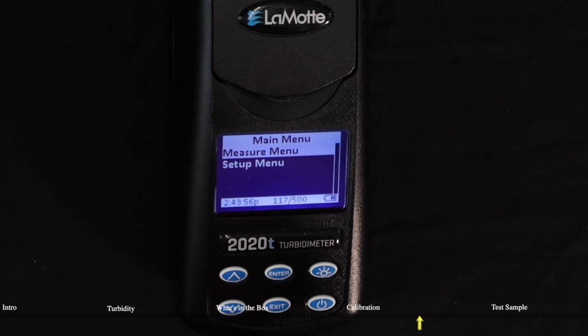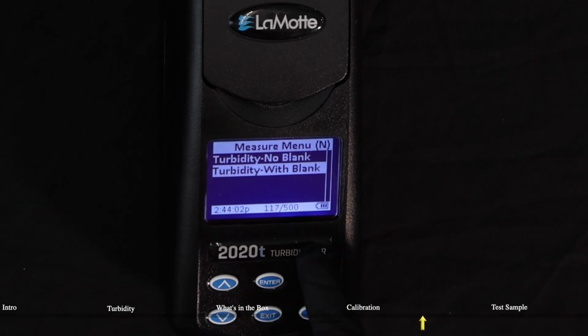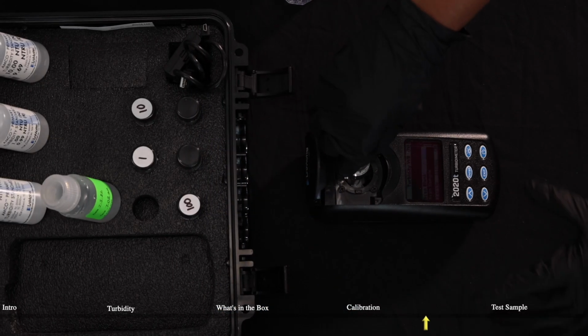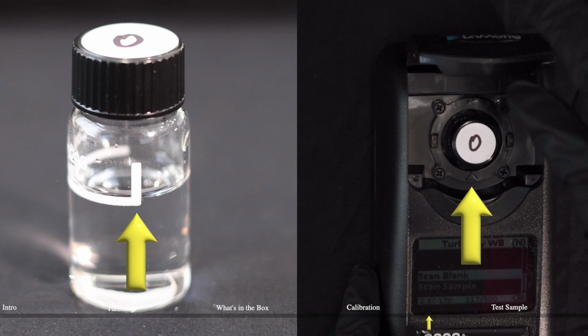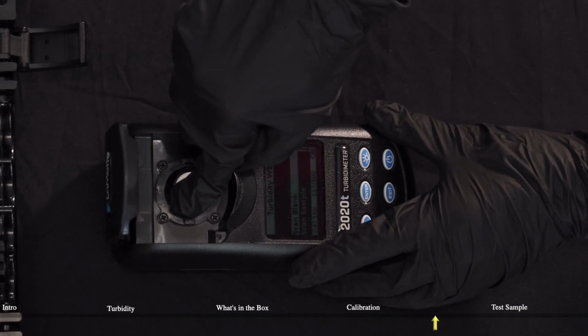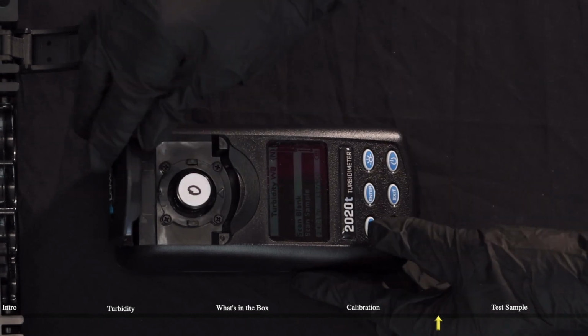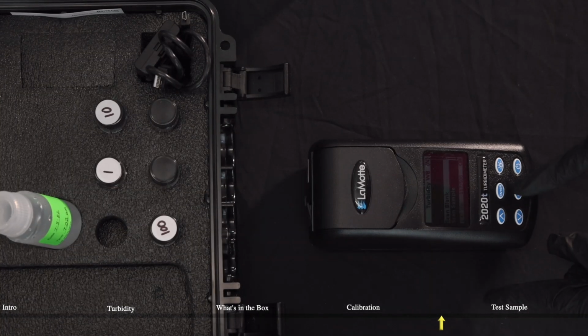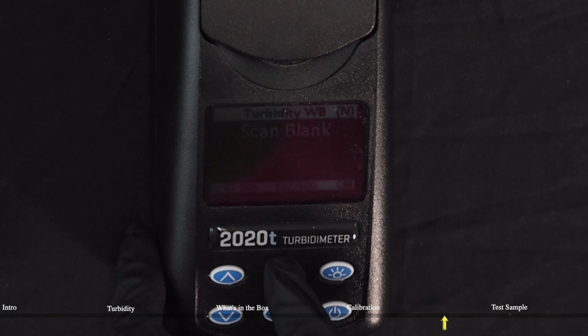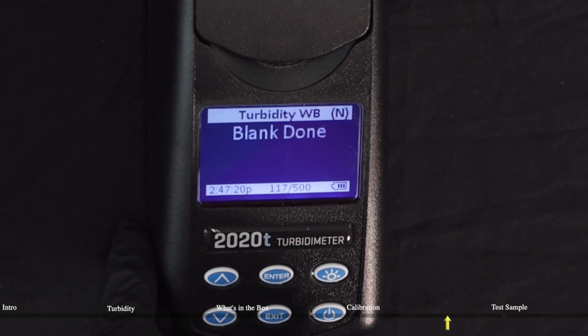Select Measure, then select Turbidity with Blank. Insert the bottle you just filled with the blank standard, making sure the white line lines up with the arrow. Now give it a courtesy push to make sure it's all the way in. Close your lid and then press Enter. Give it a few seconds, then the meter will read blank done. Remove the bottle and dump out the blank.